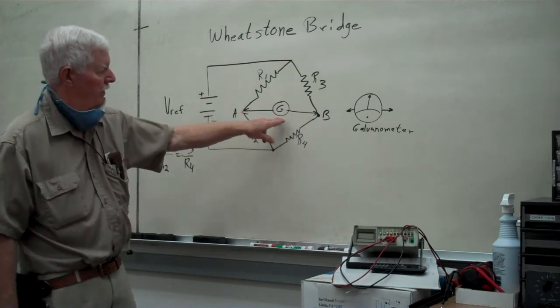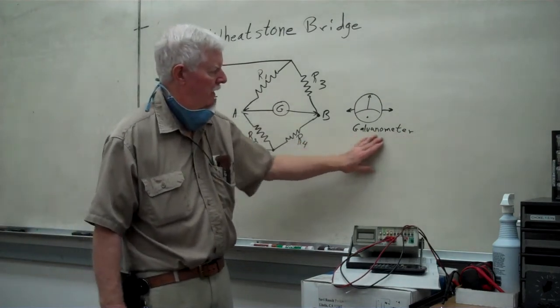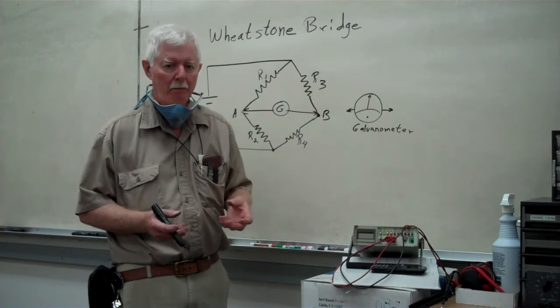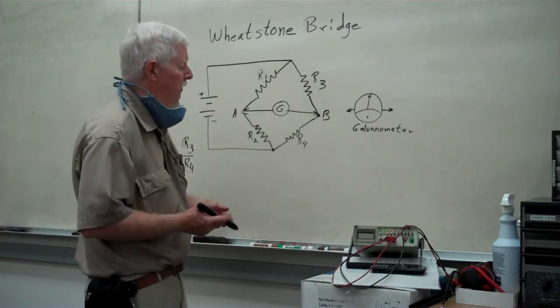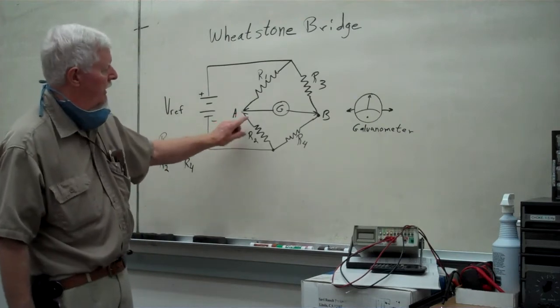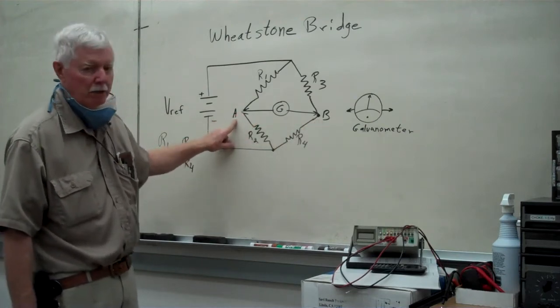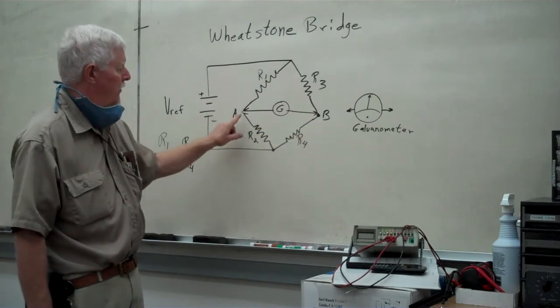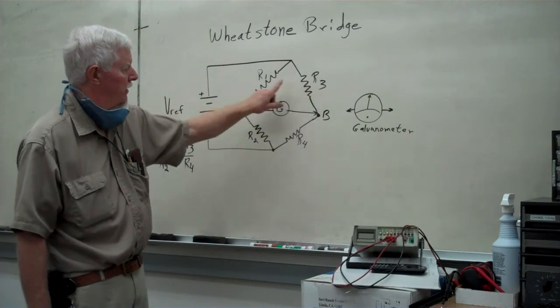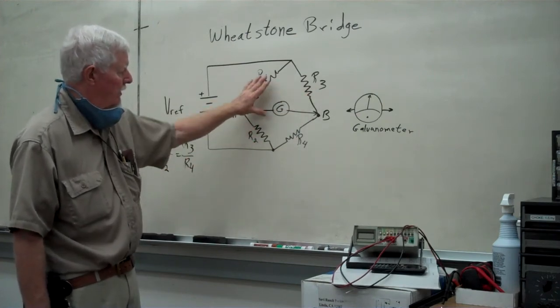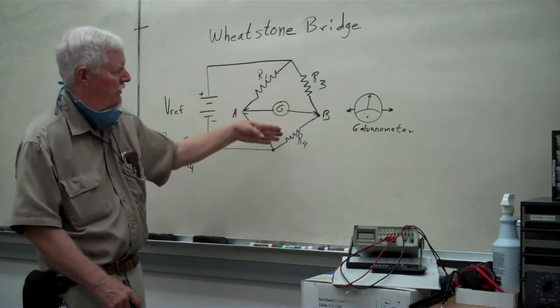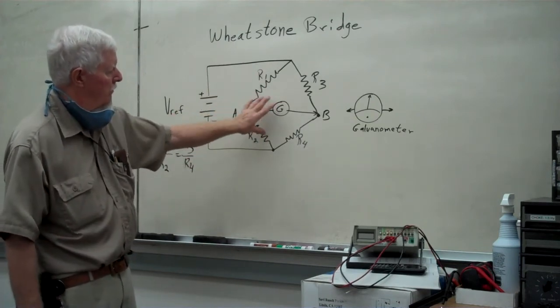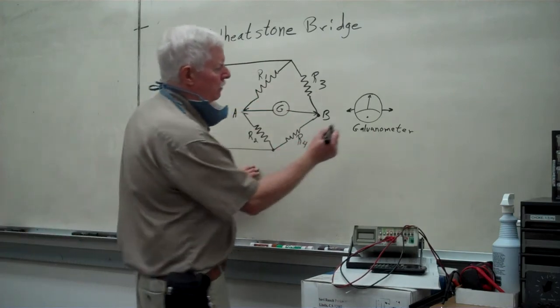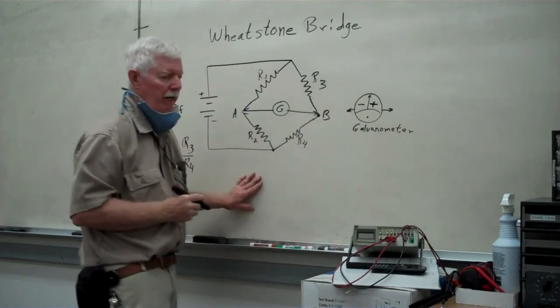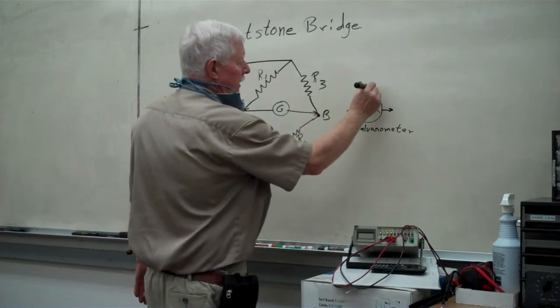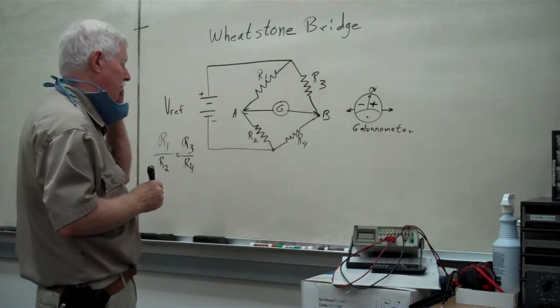This indication device is called a galvanometer. It's a zero-centered milliamp or microamp meter, very sensitive, and it detects any shift in the voltages appearing between A and B. That's going to occur if something changes in one of the branch resistors, causing an off-balance due to the difference in currents going through the two arms. It can cause the meter to go positive or negative. When they're exactly equal, you have 0 voltage, 0 microamp, 0 milliamp.